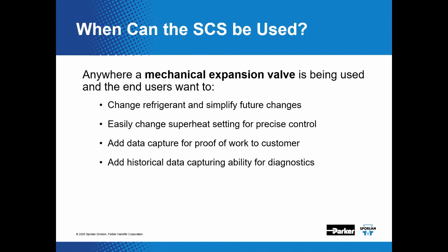It's going to provide a way to simplify changes if the refrigerant may be changed in the future, because the refrigerant type will be stored in the controller, so you can easily move from one refrigerant to another without changing out elements, valves, or things like that. Also, if refrigerants were to come out in the future and your current controller does not support it, this controller supports the ability to do firmware updates in the field without changing out the controller. That can be done through our Sporlan Tech Check app.